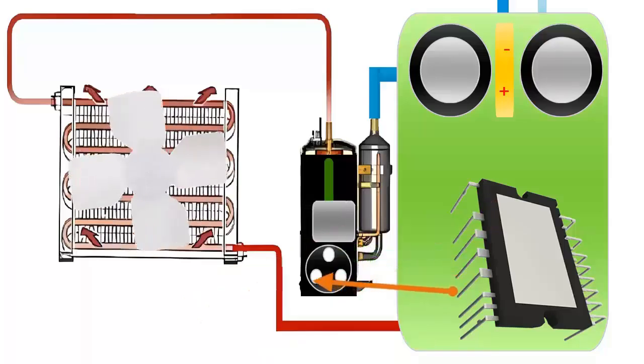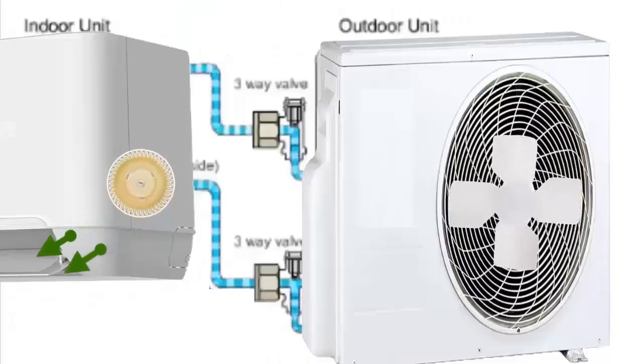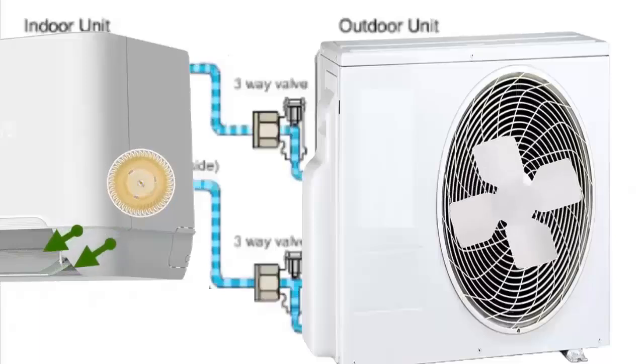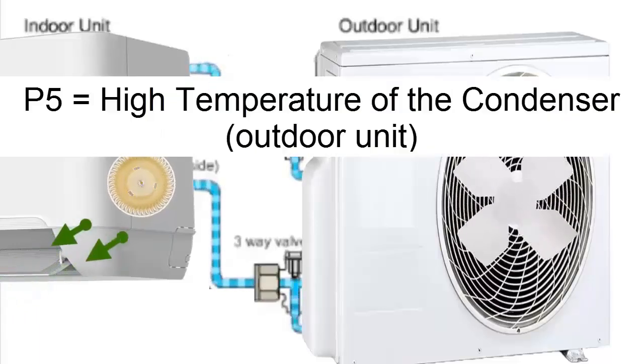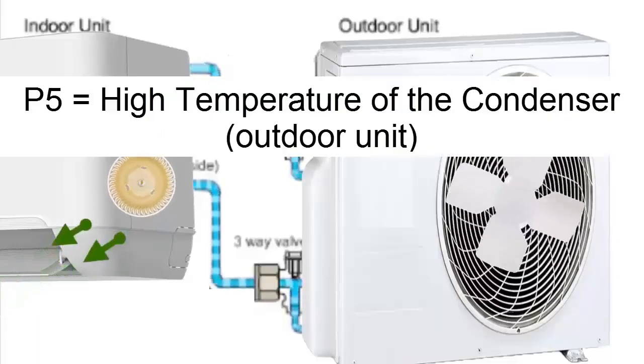However, for Midea units with HRDN series outdoor units, this code indicates protection of the condenser from high temperatures. Recommendations: A. Clean the condenser and remove obstructions from the ventilation grills, and check the rotation of the outdoor unit fan.